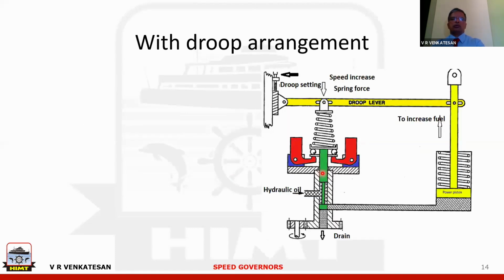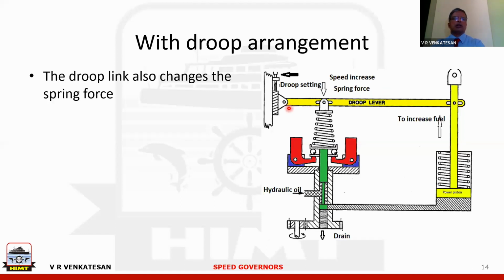So how this change happens is like this. This is called the droop link or the droop arrangement, this extra part. This was not there in the previous drawing. What happens with this, you can see very easily: if the load increases, speed will come down, the pilot valve will go down, the hydraulic oil will flow like this, and fuel is going to increase.